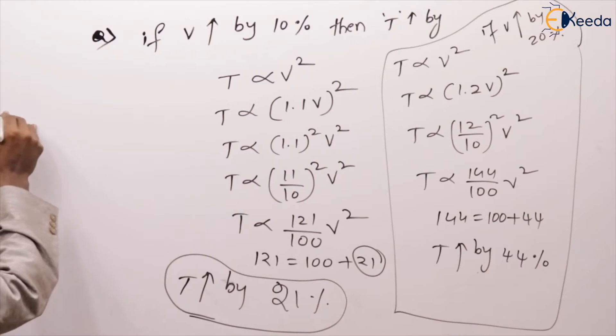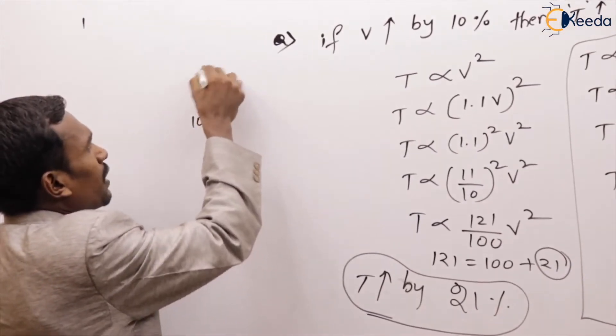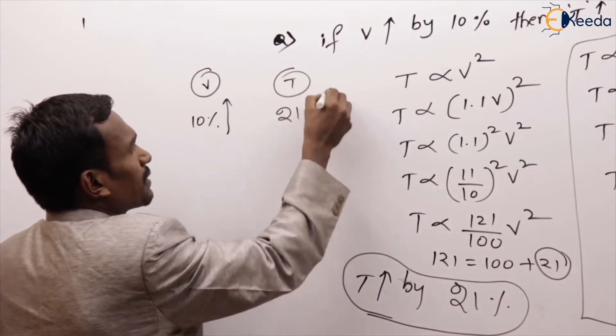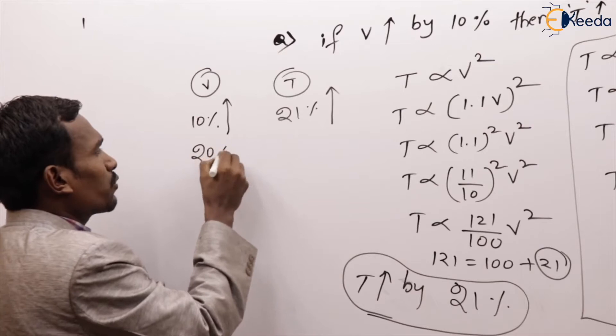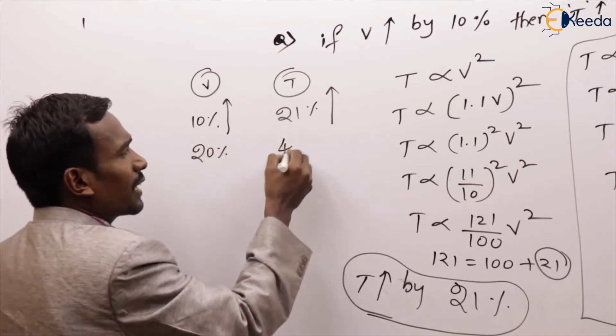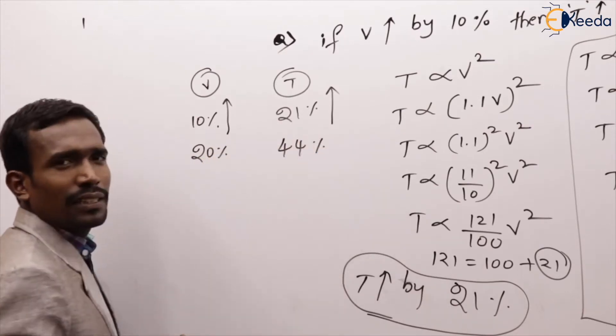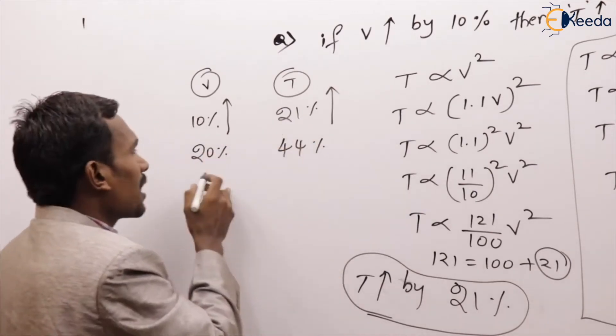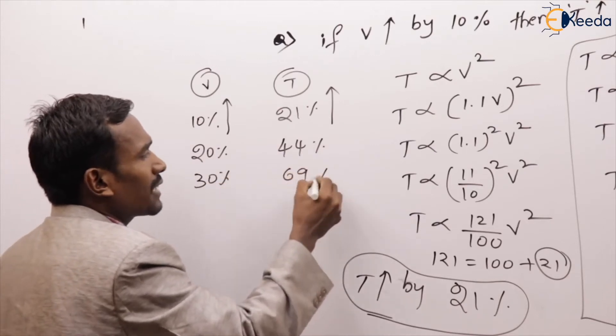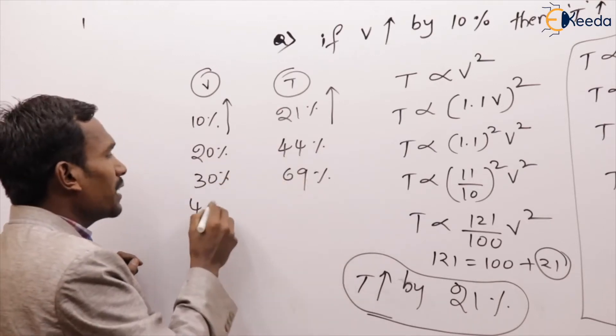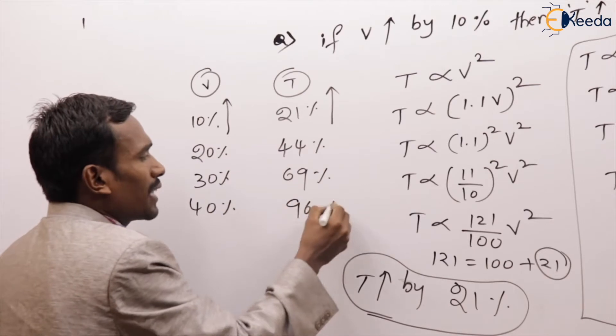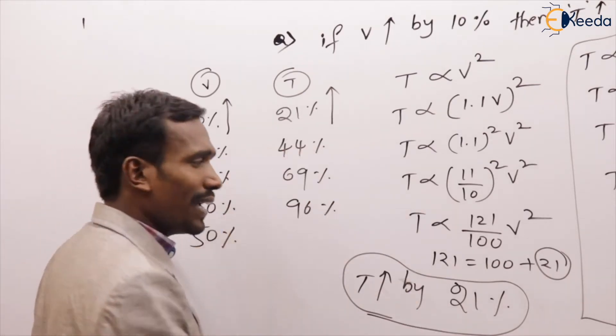See here: if voltage increased by 10%, torque increased by 21%. If voltage increased by 20%, torque increased by 44%. For 30%: 13 squared = 169. For 40%: 14 squared = 196. For 50%: 15 squared = 225, which is 100 plus 125.